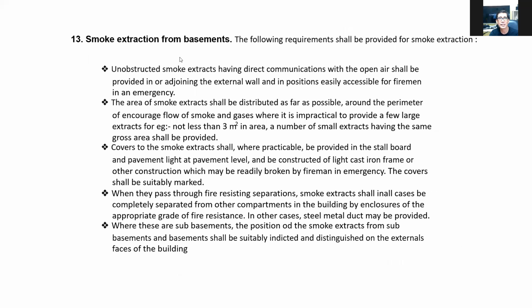So 13, smoke extraction from basements. The following requirements shall be provided for smoke extraction. Unobstructed smoke extracts having direct communication with the open air shall be provided in adjoining or external walls, in a position easily accessible for firemen. So you need to put a smokestack on the basement so that if the basement catches fire, the smoke will escape through the smokestack.